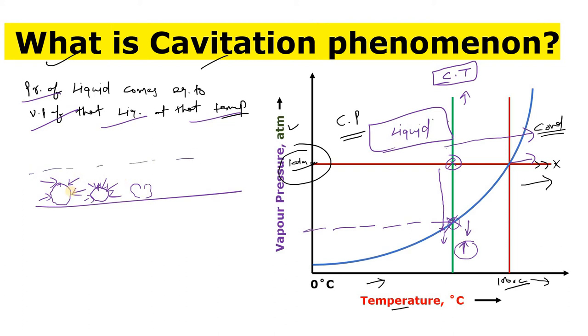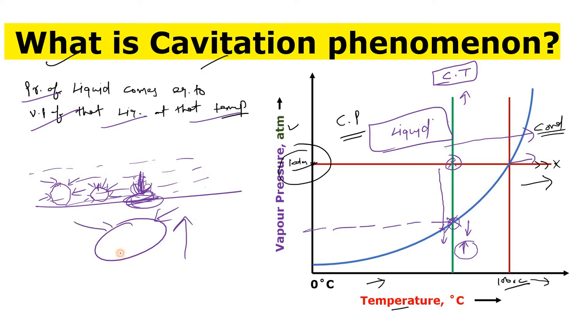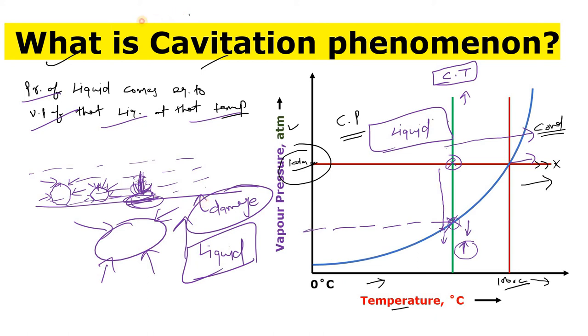This is all happening inside a liquid region. As the bubble bursts, the surrounding liquid will suddenly rush in to fill that space. As the liquid covers that space, the nearby surface can be damaged. So what is happening: bubbles form due to boiling, then as pressure increases the bubble size reduces and it suddenly bursts, the volume is occupied by liquid, and because of that your metal or surface is damaged.